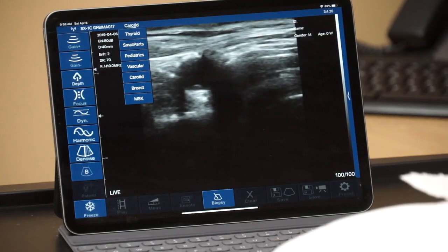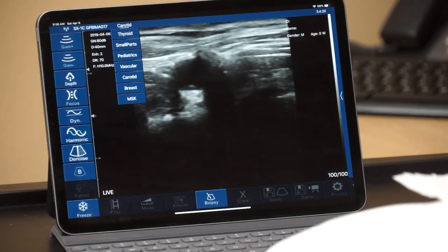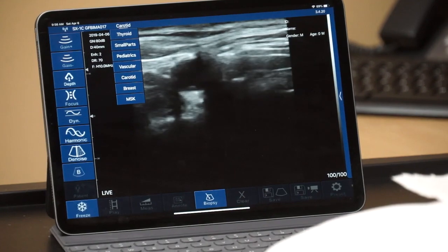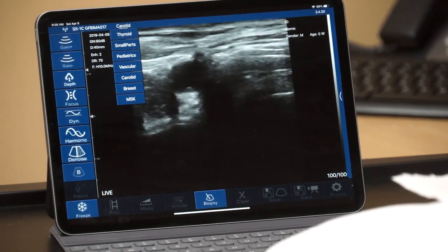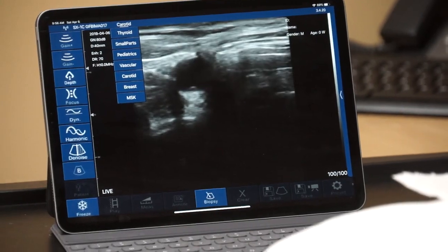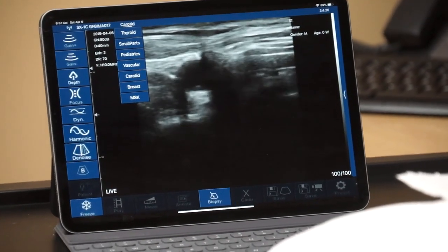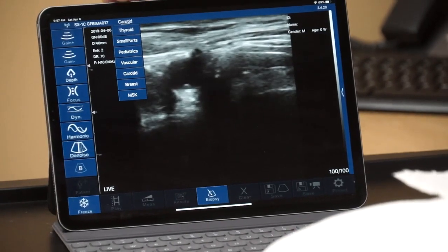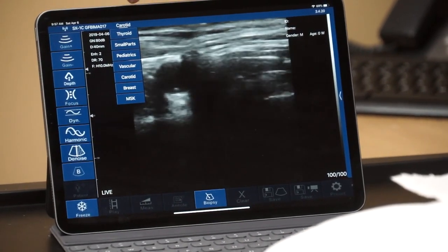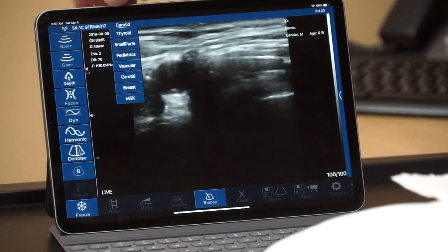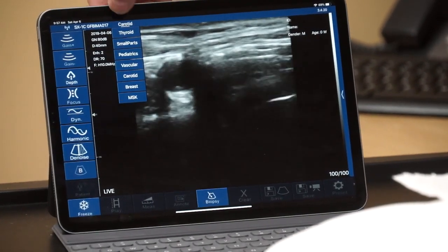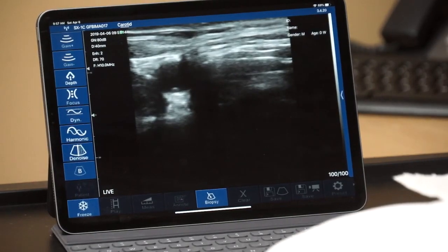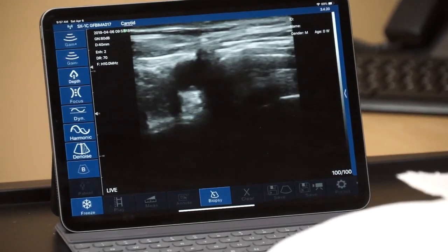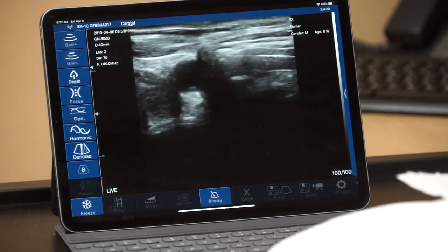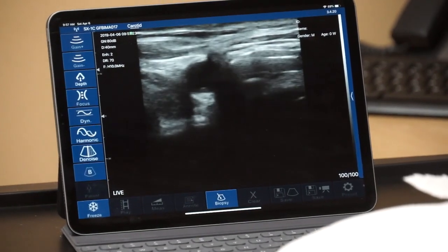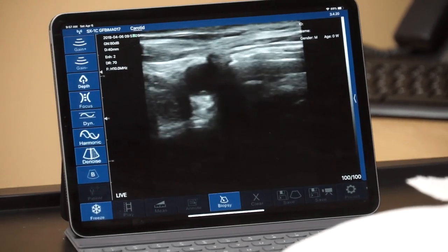So at this moment, the provider cannot pre-program their own presets, but in future updates of the software, I anticipate that we'll be able to set our own presets. I'm an anesthesiologist and I enjoy creating my own environment for my ultrasound images, so that option is coming very soon. But in the meantime, it's a very good set of parameters to guide you. Once you set what exam you want, you're still able to control them to fine-tune. So at that point, that is the final part of explaining the probe, the connection to the viewing device, the acquisition of the image, and control of the image quality.